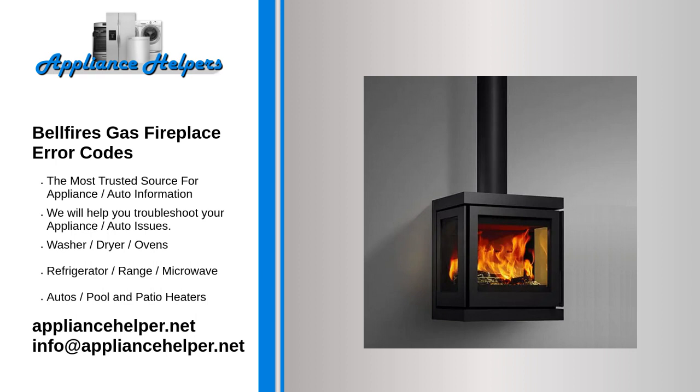Possible reasons for the gas fire going out are: 1. The concentric flue system is not installed according to one of the manufacturer's methods. 2. An incorrect flue gas restriction plate is fitted. 3. The pilot light extinguishes if fumes are not exhausted or insufficiently exhausted. 4. The pilot light is either dirty or defective. 5. Insufficient gas pressure.